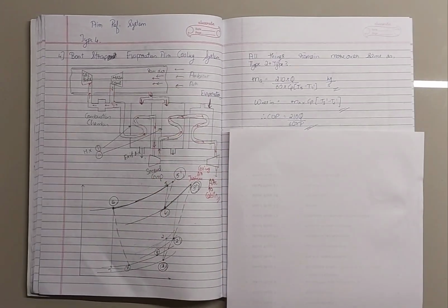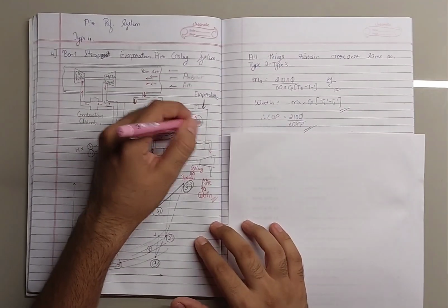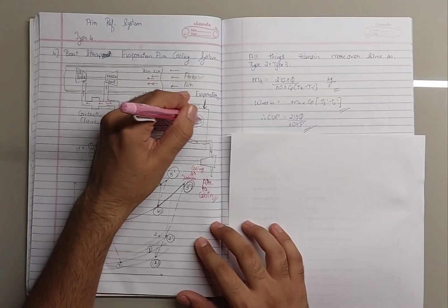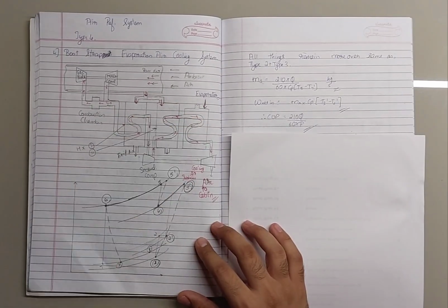The CP value of the evaporant is very high. The HFG value, that is the latent heat of vaporization of evaporant, is very high and very good. That is, it has a better character to accept the heat and cool down the opposite fluid compared to the rammed air. So it is attached here. It accepts the heat from here, it evaporates, and this cool air is passed to the cooling turbine.